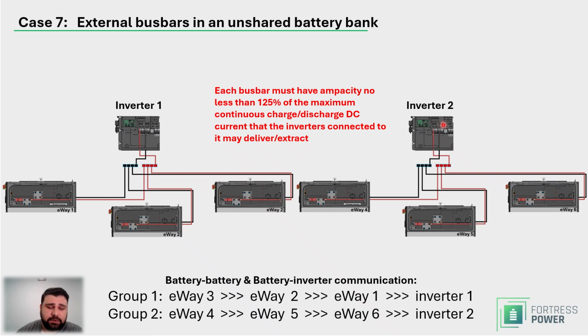So yeah, these are the principles, and I'm sure you saw the writing on the slide. Each busbar must have a capacity of no less than 125% of the maximum continuous charge/discharge DC current that the inverters connected to it may deliver or extract. So you have inverter 1 here. It can deliver 250 amps, and so these busbars would need to be 250 multiplied by 1.25. How much would that be? God, I'm too tired. I'm not going to do that math now. So whatever that number is, that must be the smallest figure for you to have the busbars capacity rated at. And same applies for inverter 2.